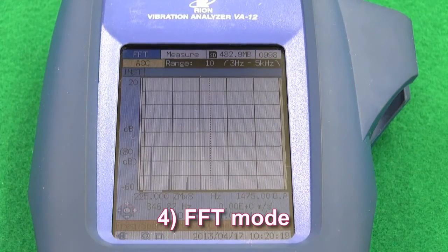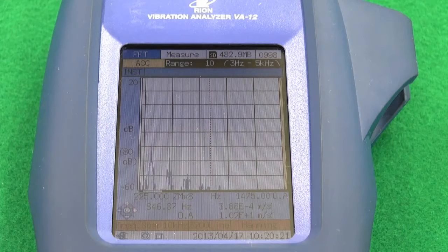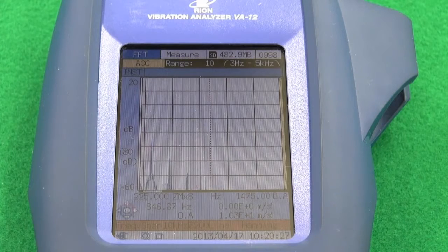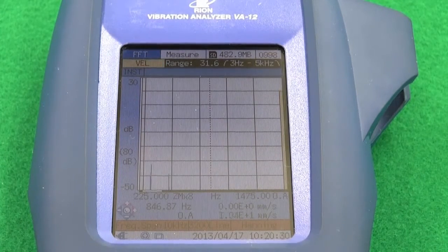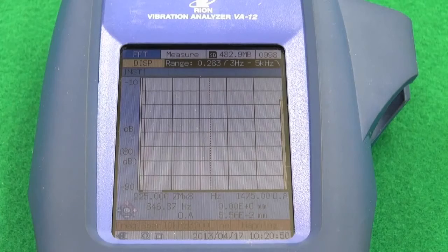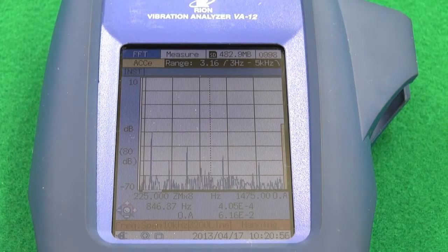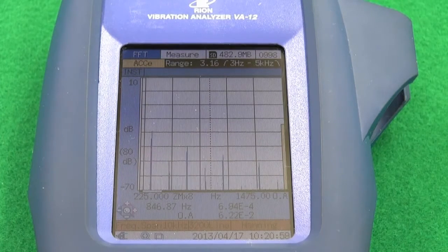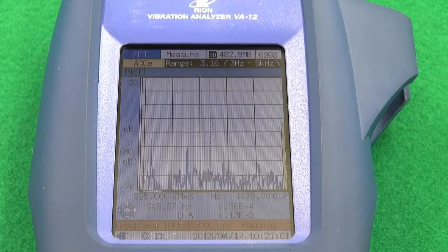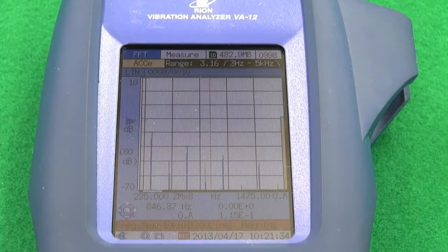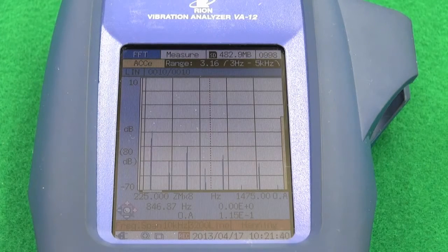Feature four: FFT mode. In FFT mode, an acceleration envelope is often used for detecting bearing faults. In this mode, acceleration, velocity, and displacement can be displayed with up to 3,200 spectral lines. This makes it possible to measure at a high frequency resolution, so vibrations that have occurred within a narrow frequency band can be detected. Wave files can be recorded, with duration dependent on bandwidth — up to 10 seconds at 20 kHz bandwidth or 2,000 seconds at 100 Hz bandwidth.